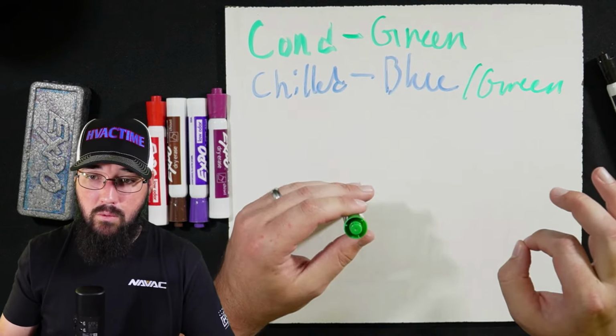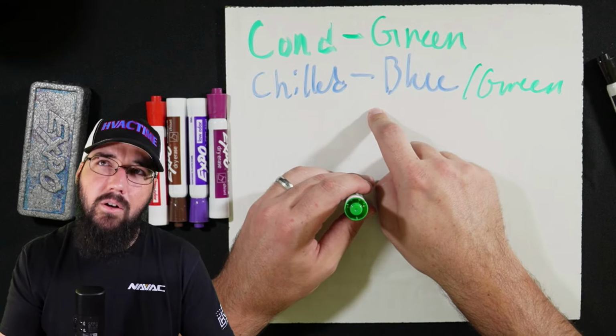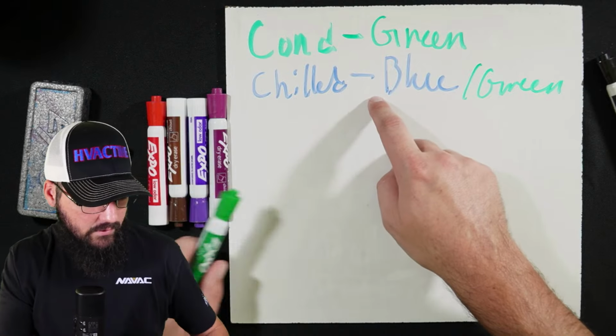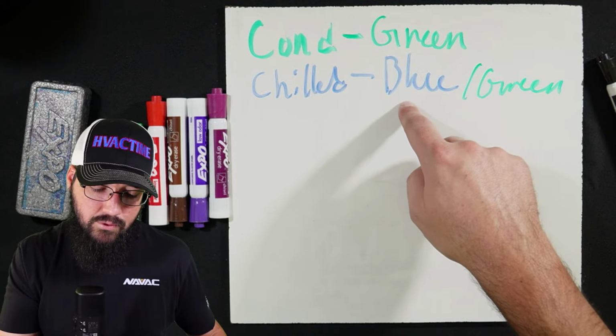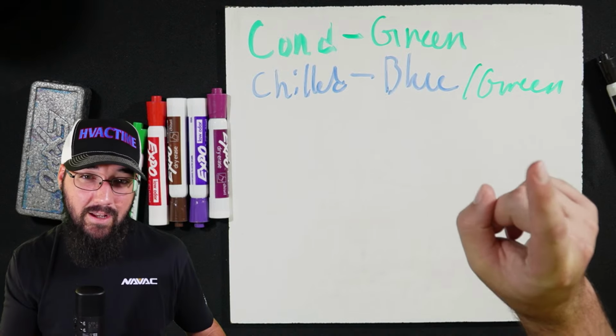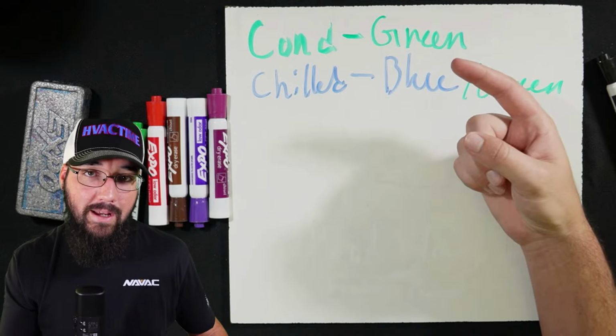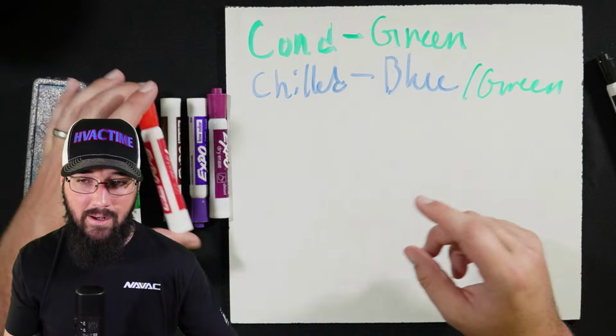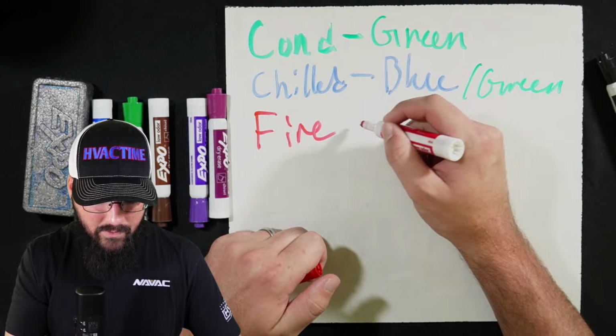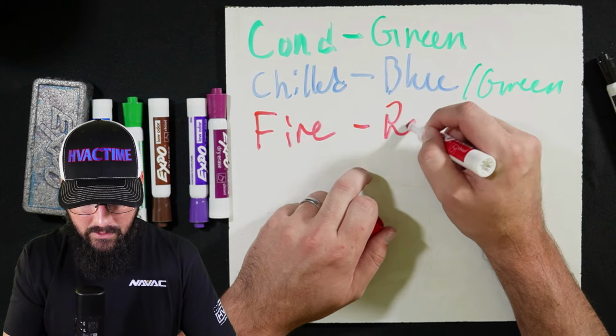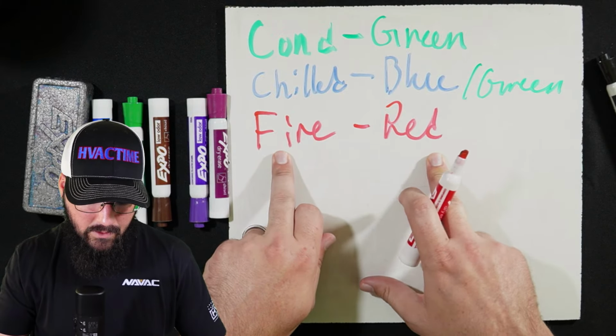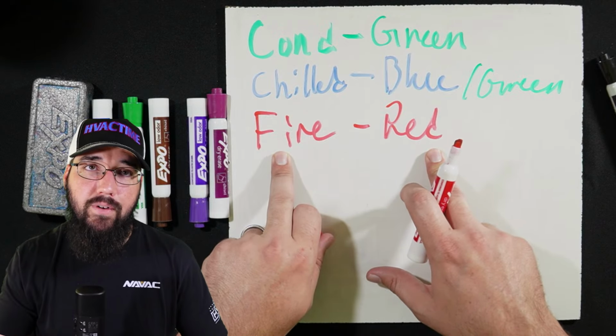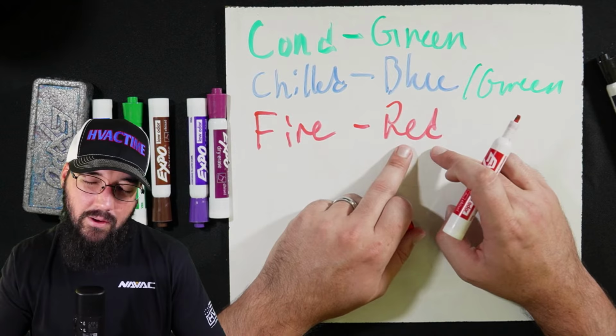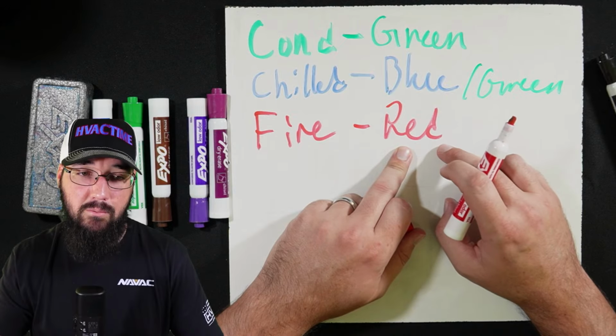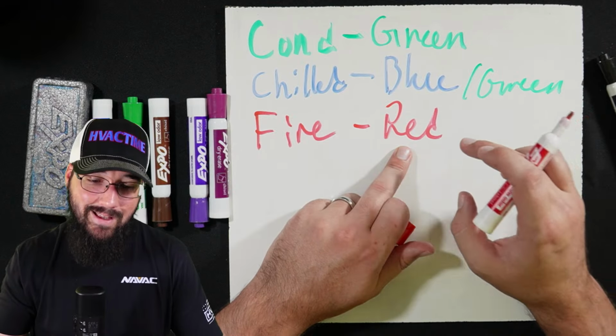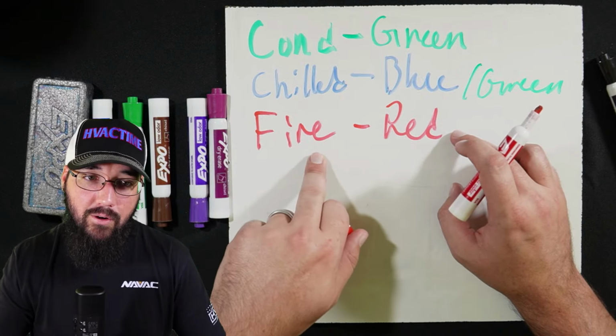Now, if memory serves, potable water is actually supposed to be blue, I think, or compressed air is blue. We'll come back to that in a second. I will tell you though, if you see chill water pipes painted blue per mechanical code standards, it's technically wrong. Now, most all of us understand what we're looking at, and it doesn't become an issue, but it's technically wrong. Now, fire is going to be red. And that's something to keep in mind: if you have what they call a tri-water loop, where your fire and condenser water are in the same, then I think they still label that as red because it is still your fire system just tied into your condenser water loop. So if you do see a condenser loop that has red piping, it might be a tri-water loop.